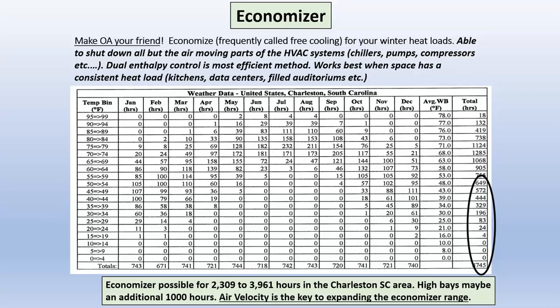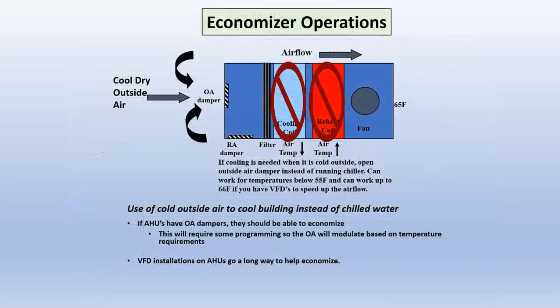One thing I learned, air velocity is the key to expanding the economizer range. What that means is, I had a situation once where when I got up to like 58 degrees, the complaints would start coming in and people said they were getting hot. And I thought, well, how can I open up this economizing window? So what I did, I set my VFD speed in a relationship with outdoor air temperature. And I started cranking it up. And I was doing my big experiment at 62 degrees, the phone started ringing. I thought, oh, they're complaining again. Yeah, they were complaining. They were complaining they were cold because, as you learn over time, personal comfort is really a function of air velocity and humidity. It's not as much temperature as people think. So by cranking that speed up, you can get away with a lot more in your economizing range.